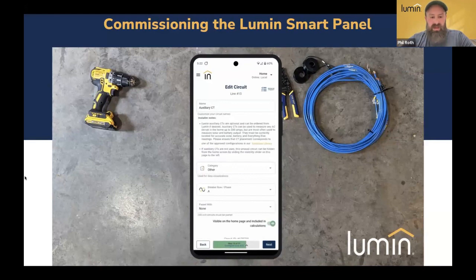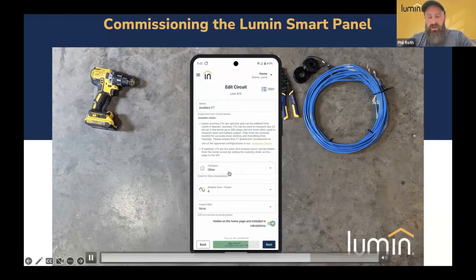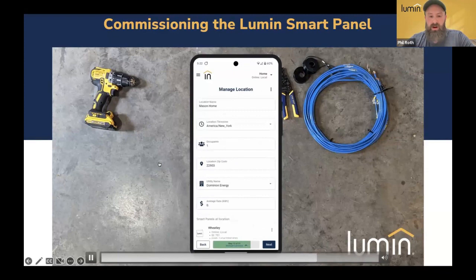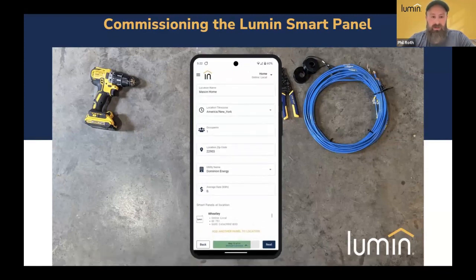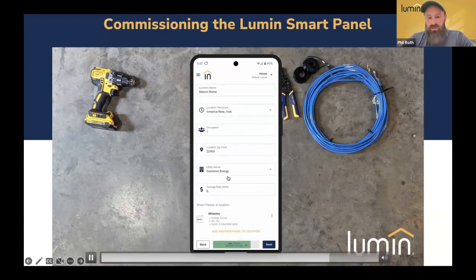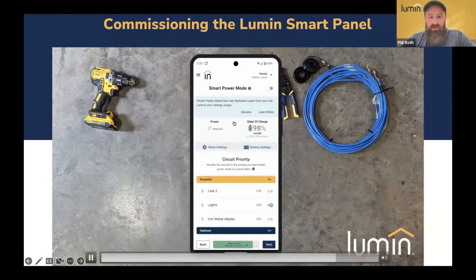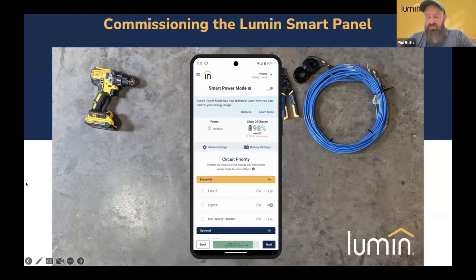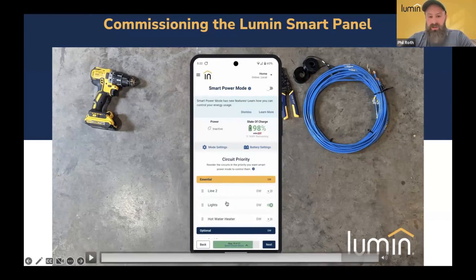This is the main CT and aux CT commissioning that Kenny mentioned earlier, which will give you all your other consumption data for ungoverned loads. Put in your utility information, your zip code, your time zone, hit next, and now you're pretty much done with the commissioning. At this point what you have left is your backup mode settings, where you can set the priorities of your Lumin controlled loads. We'll talk more about that in a bit, so I'm not going to spend a ton of time on it. You can also do your battery integrations from this screen as well.